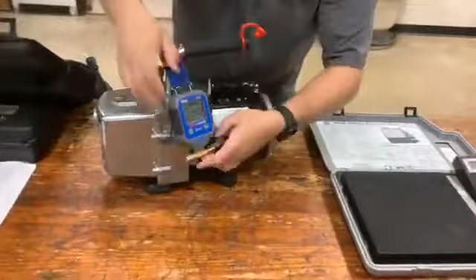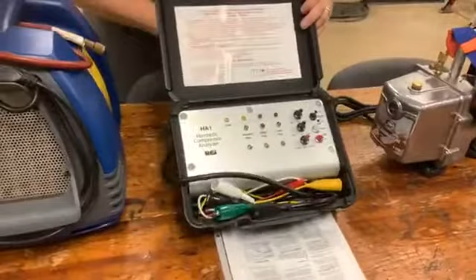A vacuum pump with a micron gauge, so you're down to at least 500 microns, the industry standard. This is a compressor analyzer for 5 ton or less single-phase compressors. You can tell if it's gone to ground, if your windings are open, and you can even start the compressor with this thing.